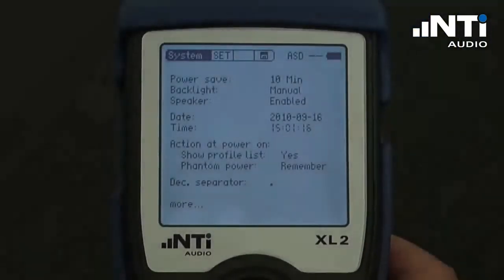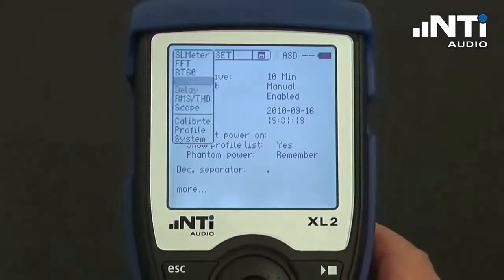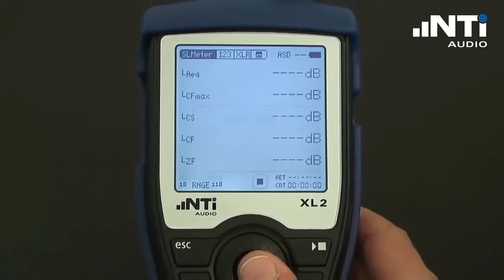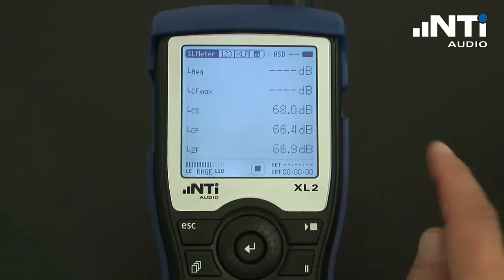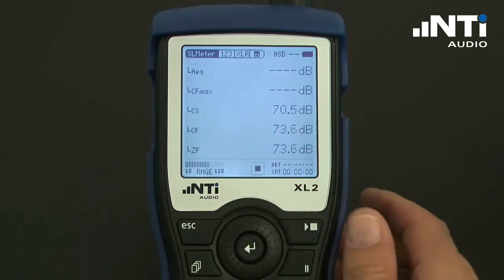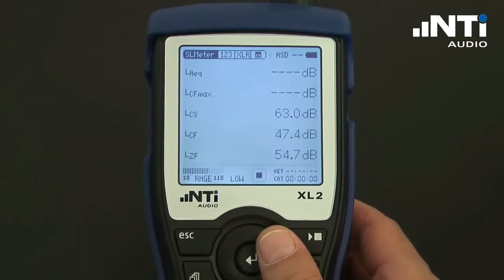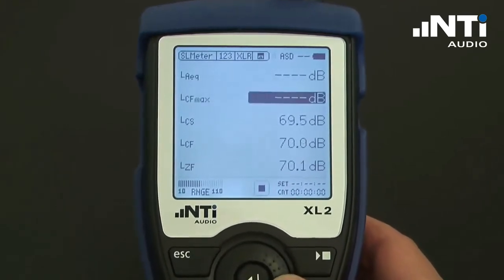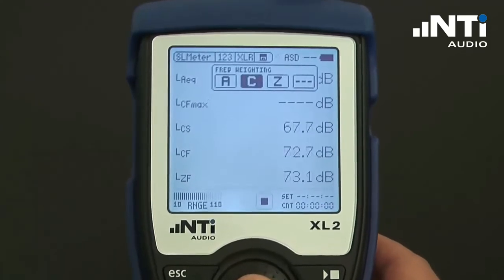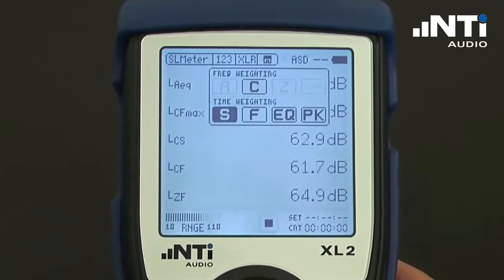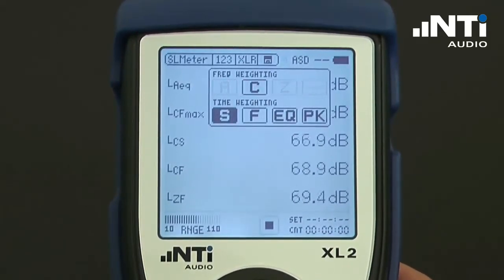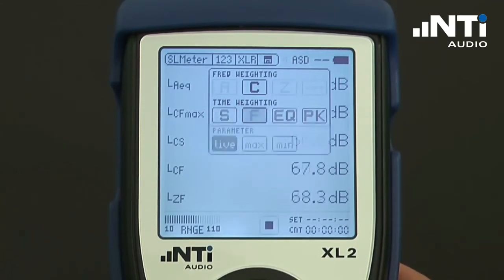For starting the sound level meter, the operator selects the appropriate measurement function. The system can also be programmed to automatically start up in this mode. As soon as the function is started, the sound level meter shows all the instantaneous values. We may choose to change them by selecting A, Z, Slow, Fast, EQ, and Peak — we can freely choose them and confirm.